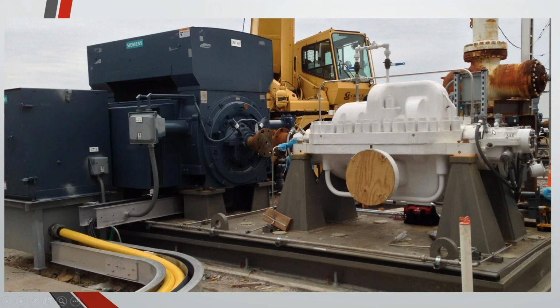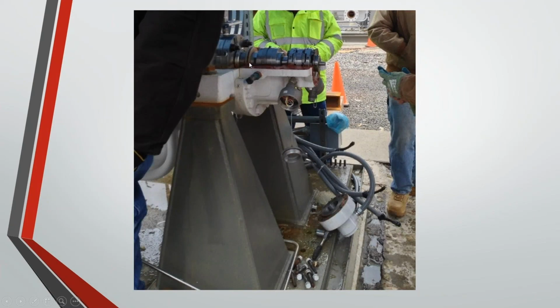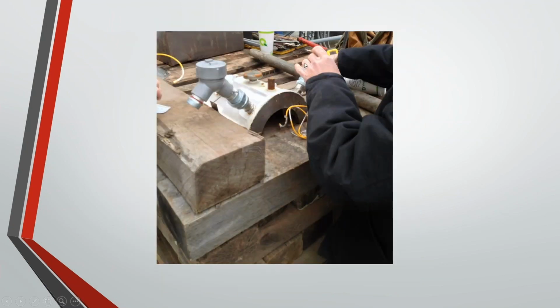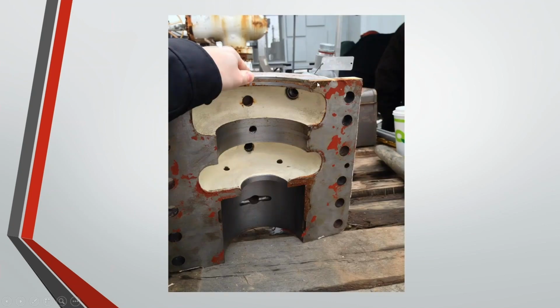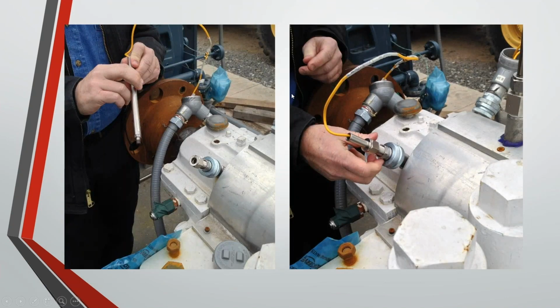So I'm going to take you through a couple of pictures and show you what that looks like inside. Here we've got the bearing housing taken off, and you can see the shaft and the bearing. And if we want to look at that housing with the proximity probe holders installed, that's here. We can flip the housing upside down and see that the proximity probe holders are mounted through the housing here. That's where the probe would come out, and it would come through this hole and be mounted such that it can see the shaft. And so how would we do that? We would want to make sure that gap is really accurate, right?